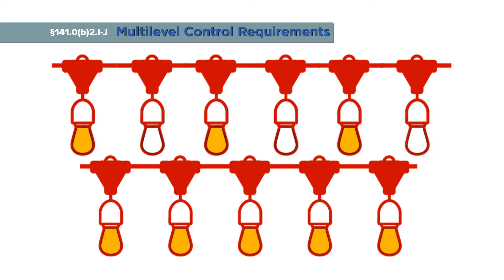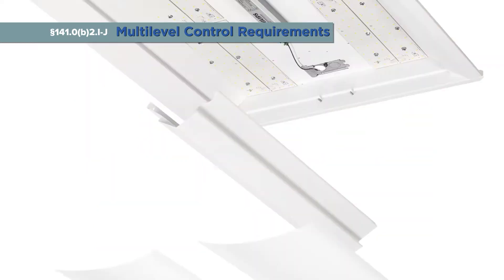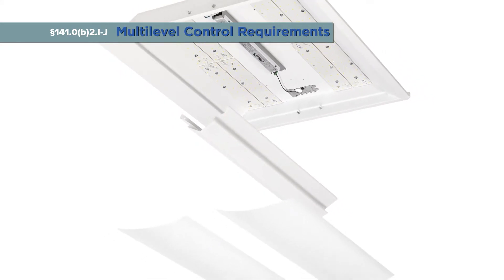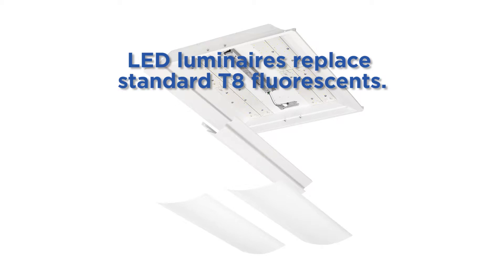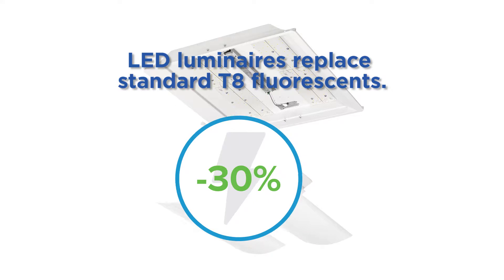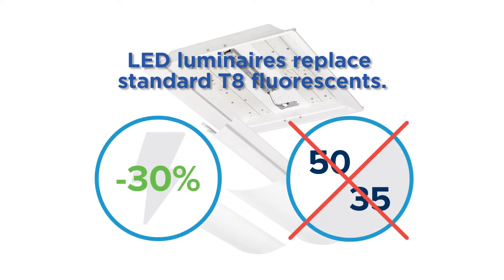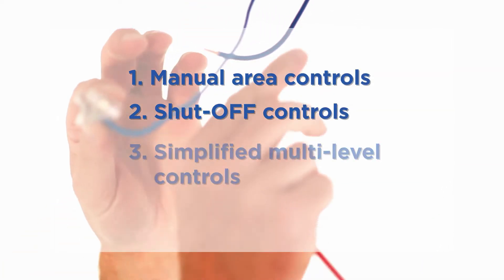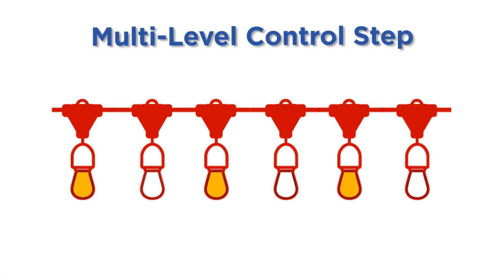Previously, each luminaire was required to have a step between 30% and 70%, which meant installation of dimming ballasts or drivers for each fixture. A qualifying project under this compliance pathway would be one where new dedicated LED luminaires replace standard T8 fluorescents. The rated power reduction is 30%, so the project cannot take the 50%-35% power reduction compliance path. However, the new lighting power is less than 85% of the lighting power allowance per section 140.6. This project must include manual on-off controls, shutoff controls, and a simple multi-level control scheme. In this example, the multi-level control step applies to the space as a whole, so controls may switch alternate luminaires or groups of luminaires — each luminaire is not required to have individual multi-level control.